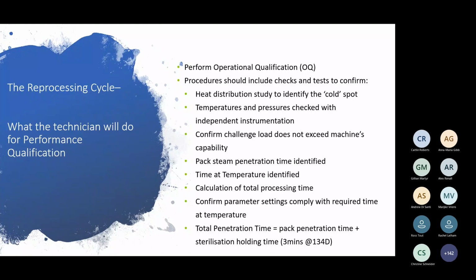So the technician basically is doing procedures that should check and confirm the heat distribution study to identify cold spot. Temperatures and pressures are checked with an independent instrumentation. Confirmed challenge load does not exceed the machine's capability, so they need to know what's happening. I think in the new standard, you're pretty much going to have to weigh your load. So that will be something extra that you will do. The technician will have to weigh the load you present, make sure that it doesn't exceed the machine's capability. And if it does, then they'll have to ask you to redetermine your load and make sure that it fits within the capability of the machine.